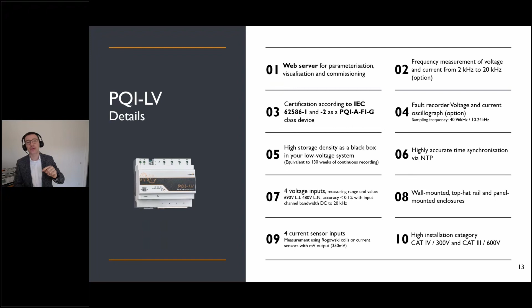We always have to think about how to handle all this measurement equipment, and the handling must be easy to install. Failure rate must be very low in case of installation failures, and the technology we provide here for current measurements supports that. As I explained, we have a very high installation category, so normally no fuse is needed. I know from the practical side that a lot of utilities will install fuses anyway, but generally no fuse is needed, and it helps reduce installation costs.